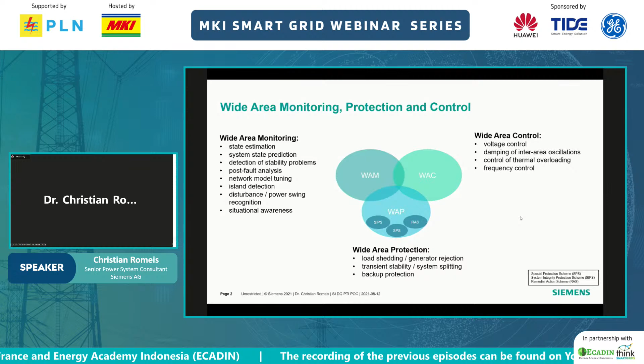On the left side is the monitoring part, wide area monitoring. You can introduce or enhance state estimation, maybe to linear state estimation. You can also introduce alarms and recognitions, such as power swing recognition or disturbance recognition, develop situational awareness, and do post-fault analysis within the WAMPAC wide area monitoring system. By introducing PMUs and collecting and analyzing data, you can get information showing problems, such as inter-area oscillations.